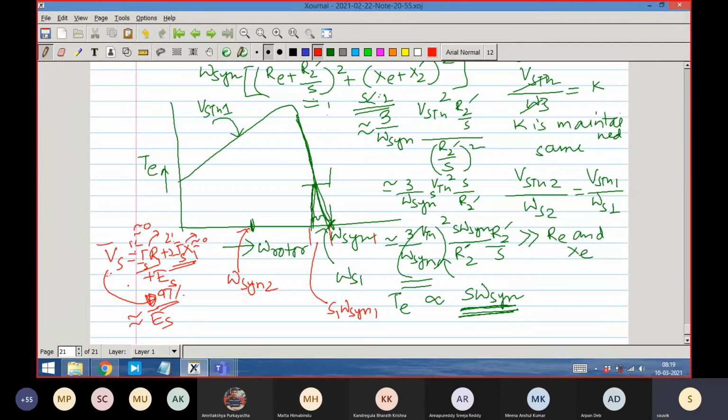You are forcing it, dictating it. You have applied voltage, you have applied frequency, so the system has no choice but to build up that flux. The consequence is that it will draw an abnormal amount of magnetizing current, and after that, further consequences follow. The machine will fail, the coils will burn, and things like that.